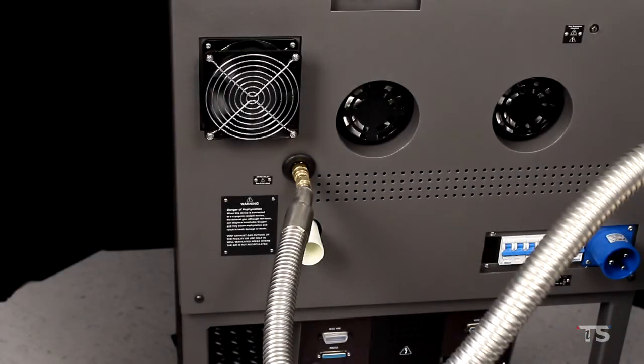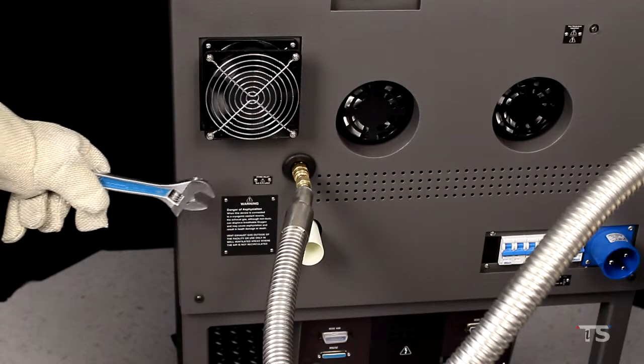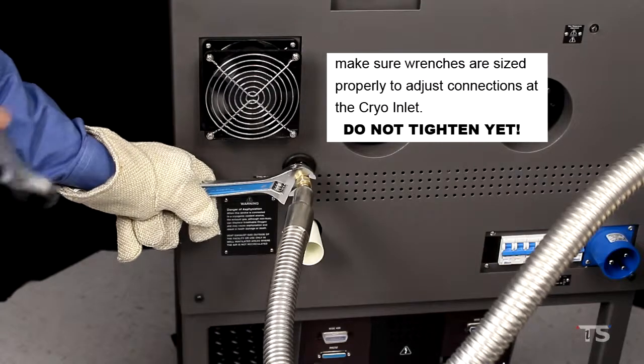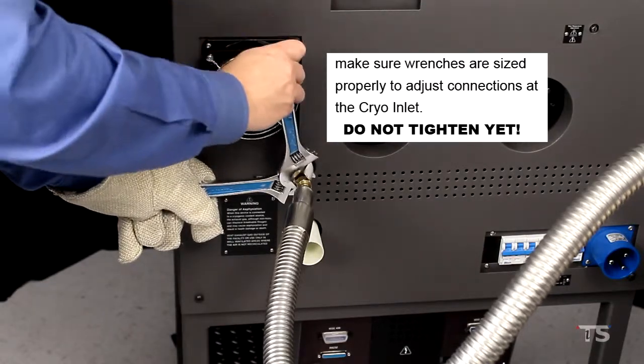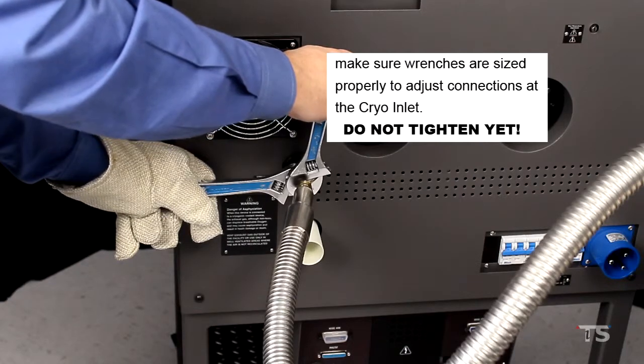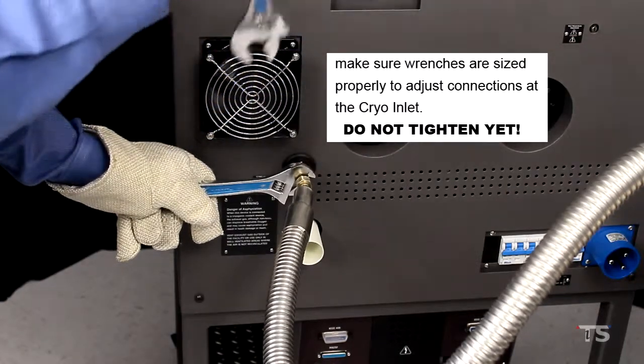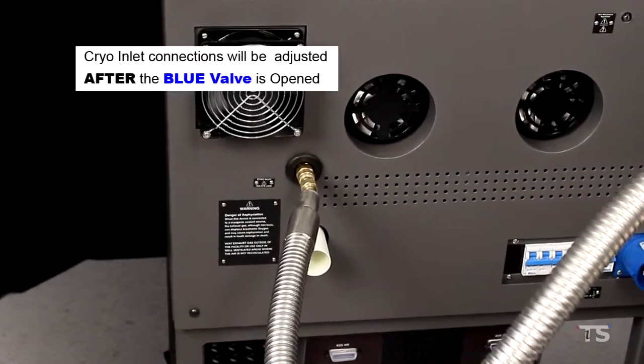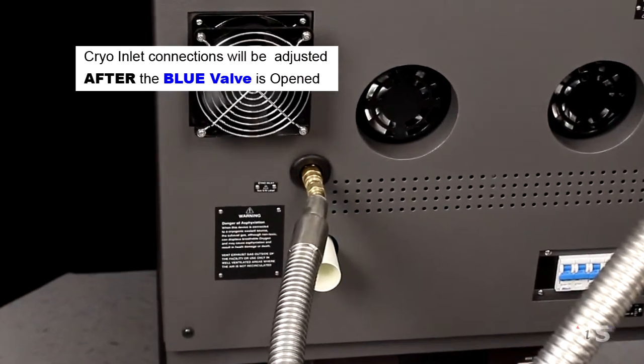Before we open the blue liquid valve and allow LN2 to flow to our thermal chamber, we need to make sure that our wrenches are sized properly to adjust the connections at the chamber's cryo inlet. We are not going to tighten the cryo inlet connections just yet. Hand-tight is what we need right now. But we will need to adjust the cryo inlet connections once the Dewar's blue liquid valve is opened.